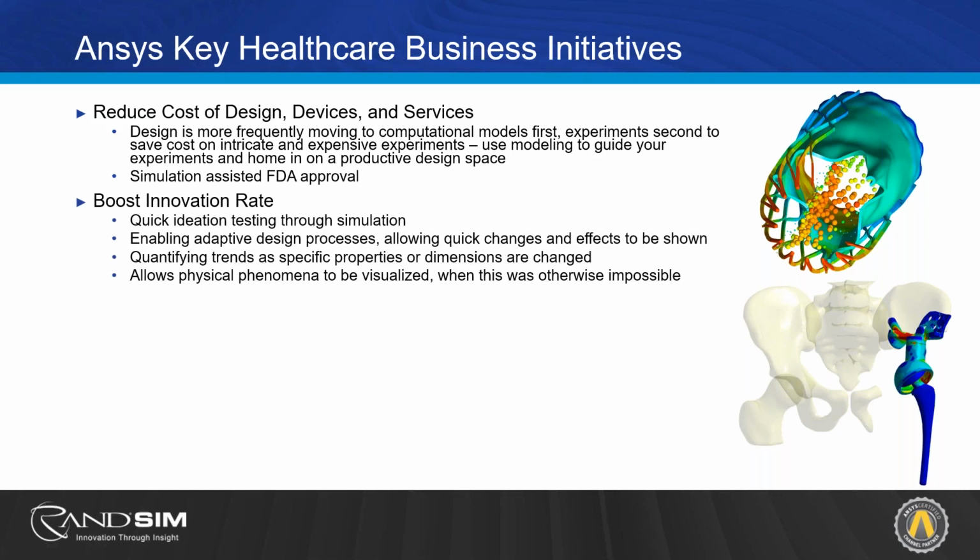Second, it can help boost innovation rates, whether it be through quick ideation through simulation. Instead of spending time setting up and building a prototype and then testing it, you can do some quick simulation models to see if it's even a feasible concept. It can also enable adaptive design processes, allowing quick changes to be made and then shown in the results and how effective the medical device might be. It can also be useful in quantifying some of those trends early for specific property changes or dimensions within your medical device in order to gain some quantitative data to help drive your prototyping into a final product.